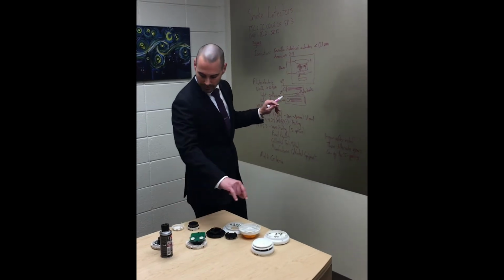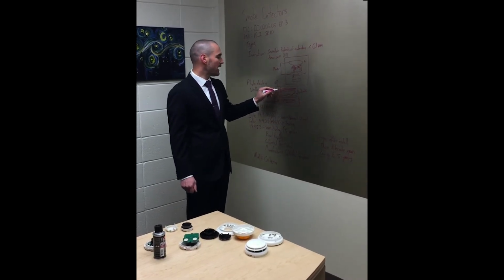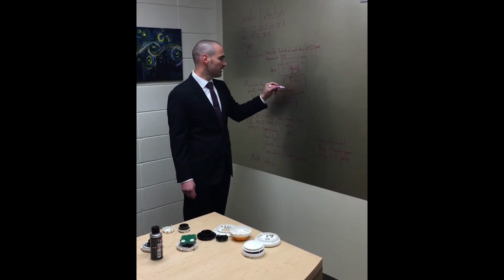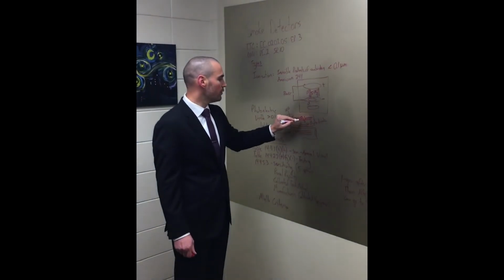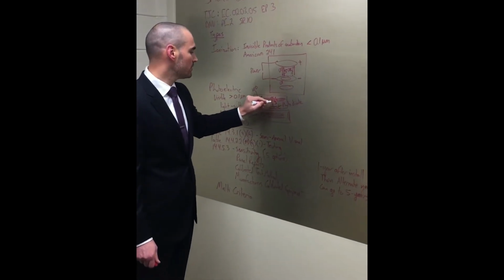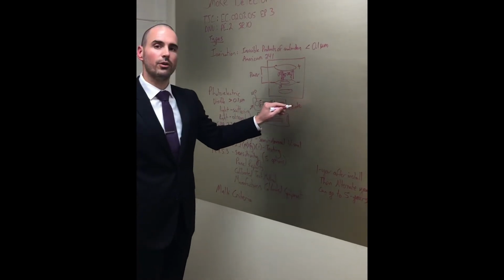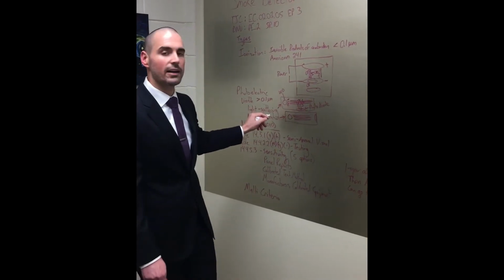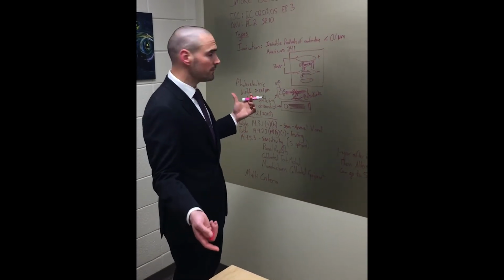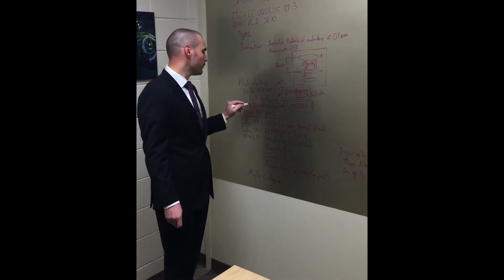How light scattering works, and that's what all of these are, is light scattering type detectors. We have an LED and we have a photodiode down below here. And that LED produces light going across. It doesn't interact with the photodiode until smoke starts entering, and then the smoke bounces the light down to the photodiode, and that's what triggers the light scattering detectors to go into alarm. That's the most common kind of smoke detector you'll find in a hospital.